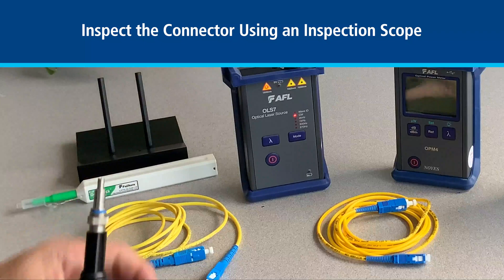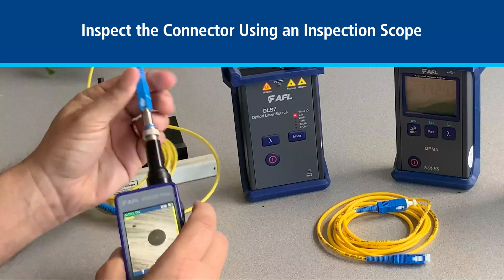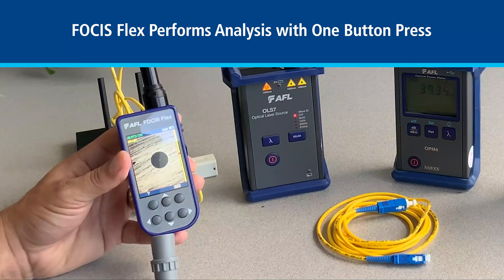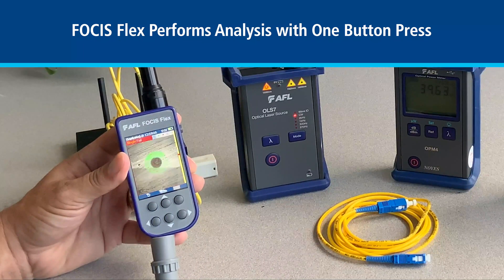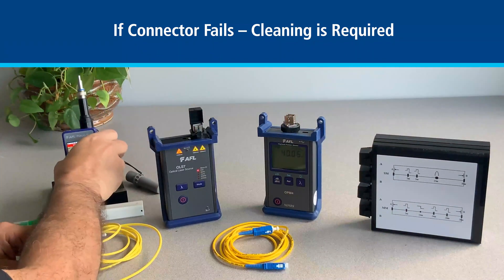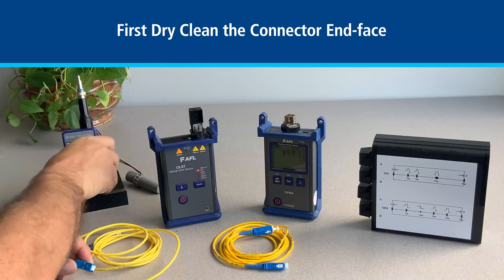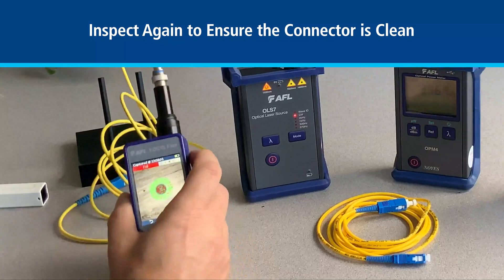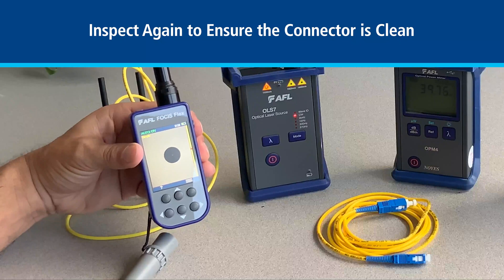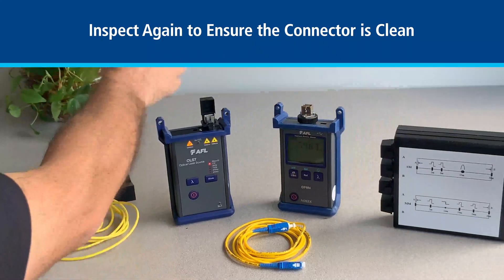Here we will use a FOCIS Flex fitted with the appropriate tip to inspect the connector. It failed so we will dry clean using a one click cleaner. Then we will inspect it again to ensure it is clean. It passed so we can connect and start testing.